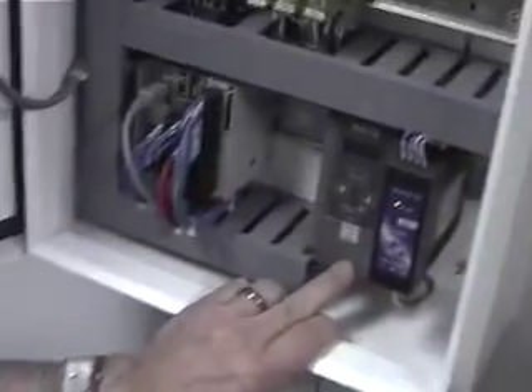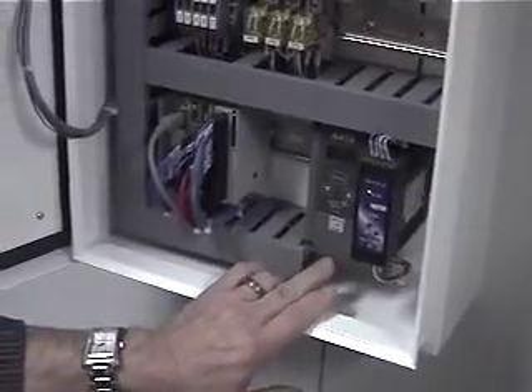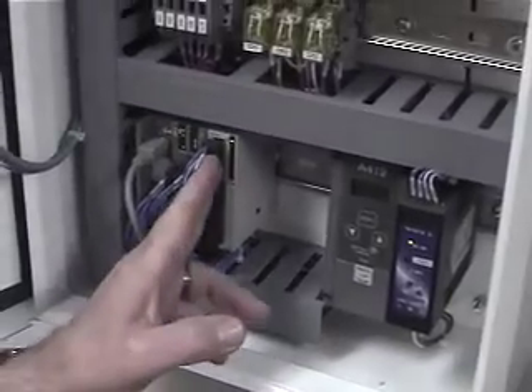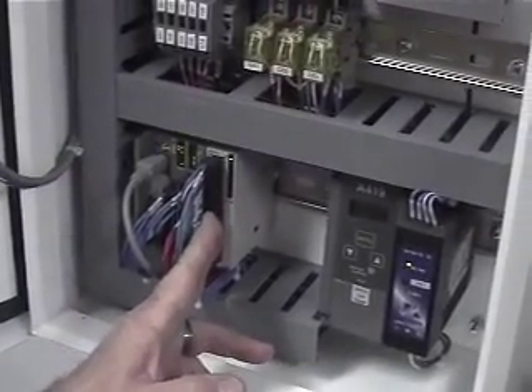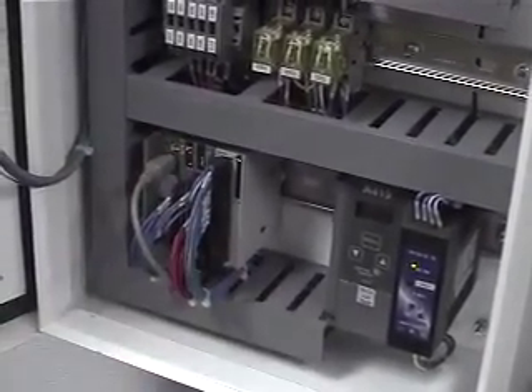But we continue to keep the room below 8 degrees with the backup alarm. We'll actually energize the fans and the liquid solenoid, and bring the room down to 4 degrees, and we'll let it rise to 7, and we'll just continue to cycle it that way, to keep the room until you have a chance to find out what the problem is, or we have a chance to find out what the problem is and get it fixed. So all your RTDs actually wire into the analog input card, and they tell the PLC what's going on. Okay. Any questions about that?